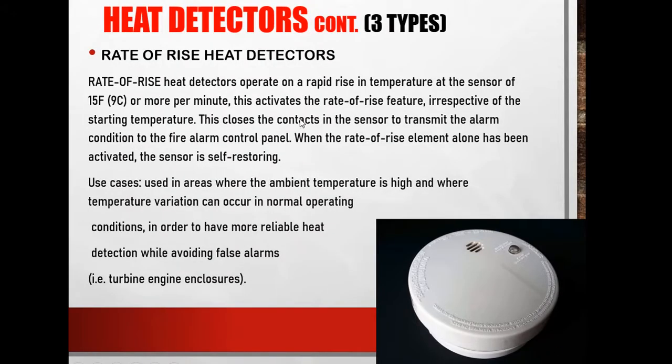Rate of rise detectors. Now, these detectors are very useful in places that are normally hot. I'm not talking of like in the desert. I'm talking of like in an engine or in a compressor where it's already over 100 degrees centigrade. How can you tell that there's a fire in such a place? Because the normal operating temperature is already over 100 degrees centigrade. How do you want to tell?